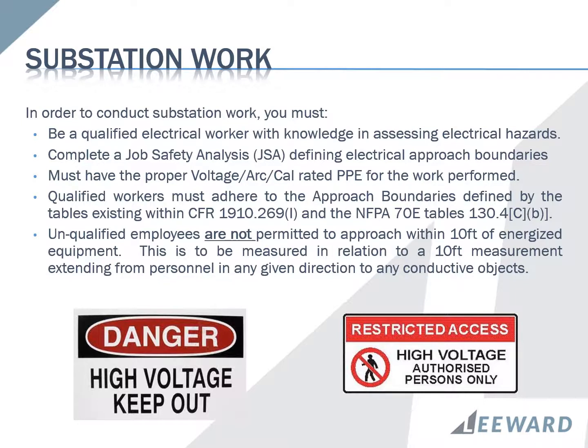Substation work. In order to conduct substation work, you must be a qualified electrical worker with knowledge in assessing electrical hazards. Complete a job safety analysis defining electrical approach boundaries. You must have the proper voltage, arc, or cal-rated PPE for the work performed. Complete a work permit defining the scope of work with Leeward supervision. Qualified workers must adhere to the approach boundaries defined by the tables within the CFR 1910.269(I) and the NFPA 70E tables 130.4. Unqualified employees are not permitted to approach within 10 feet of energized equipment, measured from personnel in any given direction to any conductive objects.